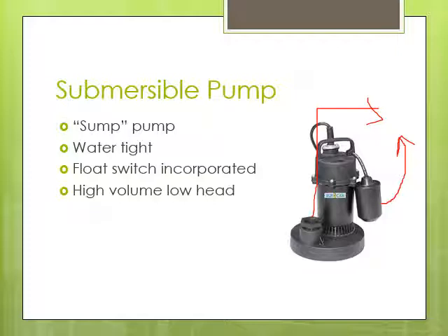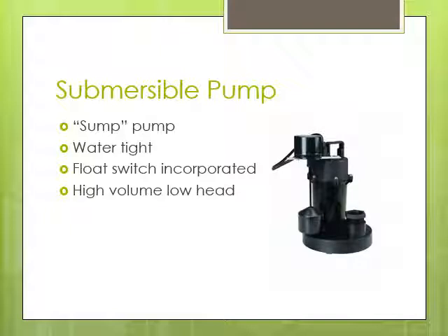Another common location for these is the loading docks where trucks are. We have to pump water out to keep them dry so trucks can back into that lower spot. Typically, these are high volume, low head pressure. So a sump pump is not a good application for irrigation if you're doing a fairly large thing.